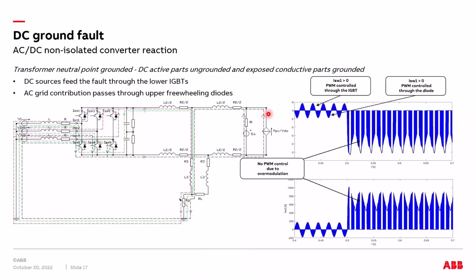But in the case of a non-isolated one, for example, it is quite common to have a DC-DC isolated converter, at least inside the DC charger. But in order to reduce the installation cost, in some cases we can have the non-isolated one as the main AC-DC converter. So in case of a short circuit or ground fault on a common load, or here, instead of a load, we have our batteries installed on our vehicle.